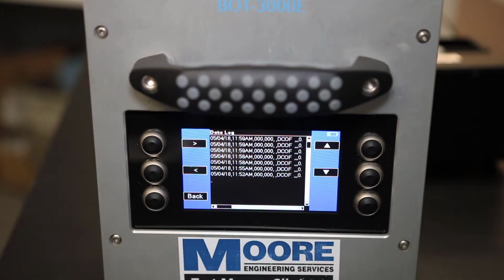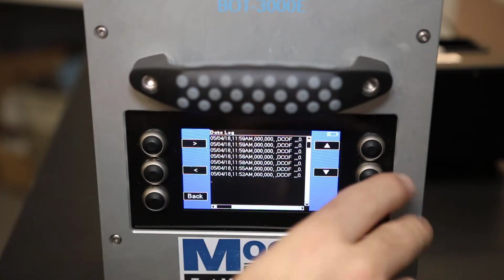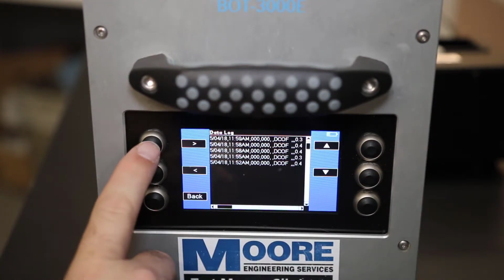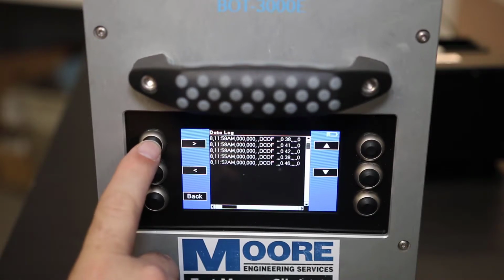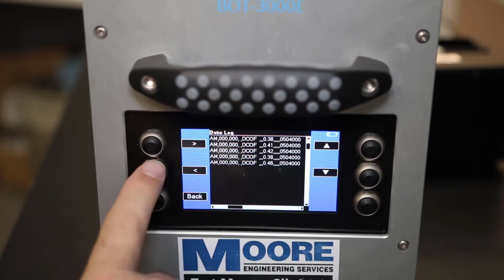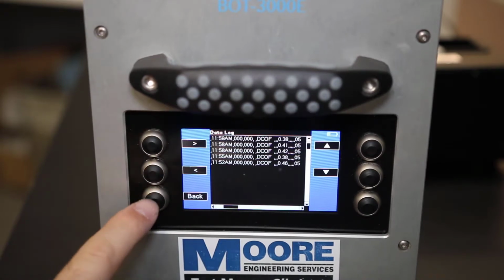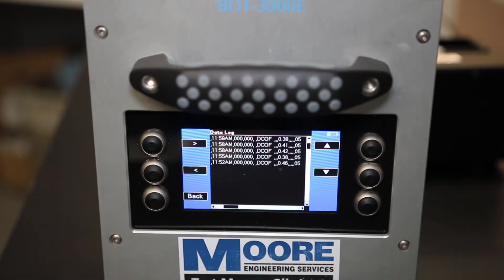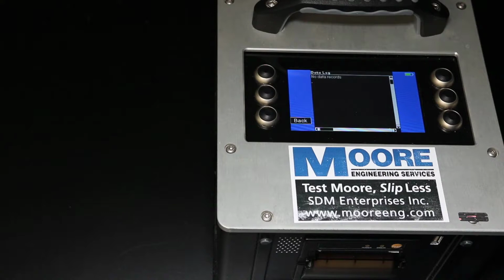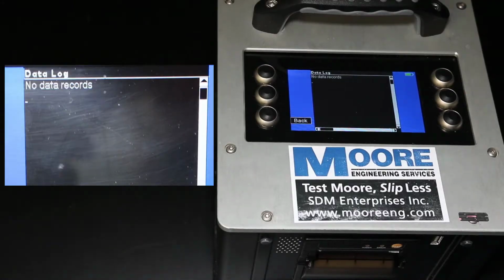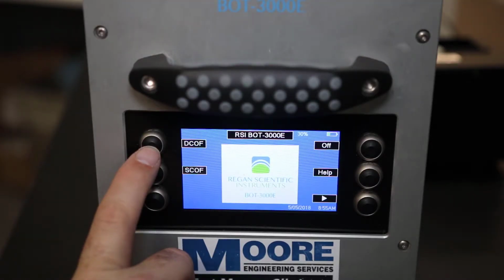By going to the Data tab, we can view the data records stored on the BOT currently. The data shows the date, time, and results of each measurement taken with the BOT-3000E tribometer. If any data is currently stored on this BOT, it will appear here on the data log screen. You can press the arrows to pan up, down, left, or right throughout the data. These measurements will make more sense later as we begin testing. If there's no data stored on the BOT, as it should be between uses, you will see the message No Data Records. Now we'll discuss the collection of data and use of the BOT.